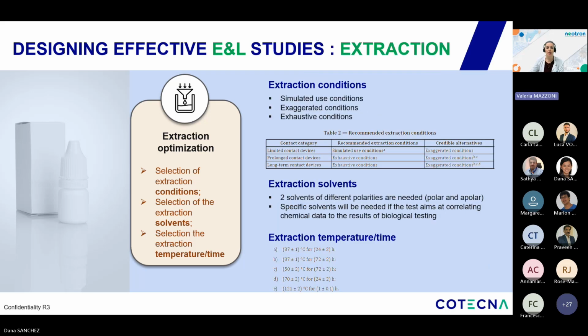Okay, so extraction optimization is essential to generating meaningful and defensible extractable data. And to do that, we have to carefully design it. So starting from extraction conditions, they can challenge the material without causing unrealistic degradation. And to do that, we can use simulated use condition, exaggerated conditions, or exhaustive condition, depending on the contact of the medical device. As a second point, we have to select the solvent.